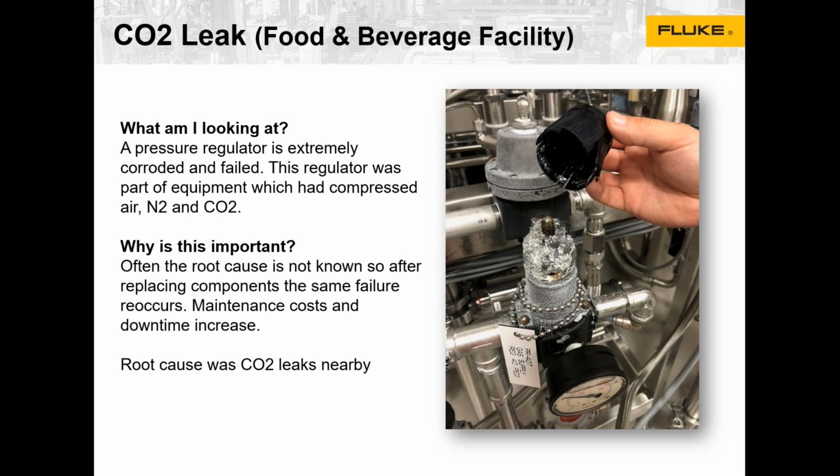They were getting some complaints about the beverage that they produce being flat. And so when we had our team on site helping them understand and start to use the technology there, they actually spotted one of those CO2 leaks, maybe similar to what was causing the corrosion on this component here. For them, that was a really big deal, because they didn't understand the root cause behind why the carbonation level for their beverage wasn't meeting quality standards. They were getting complaints from customers, and they were like, wow, we can find issues in our production line that are impacting product quality with this tool for CO2 leaks.